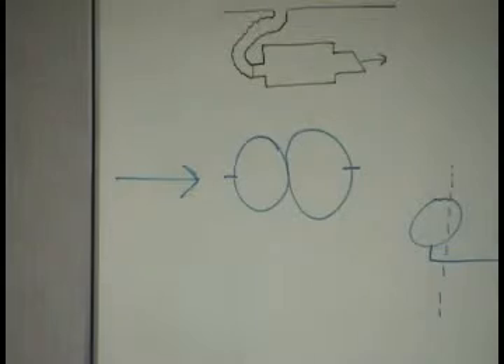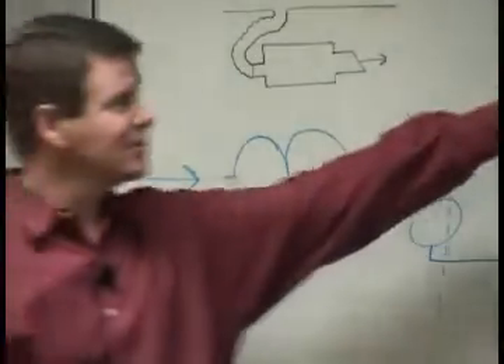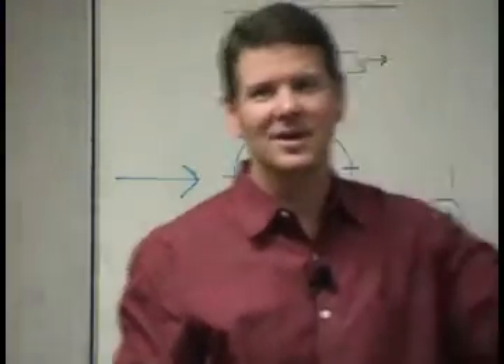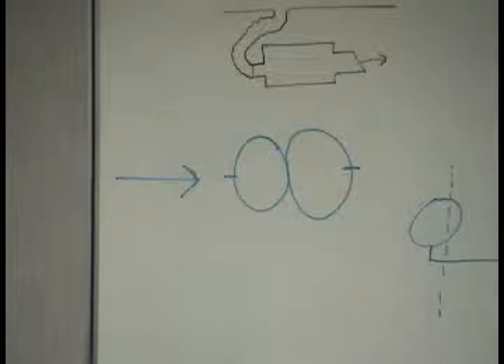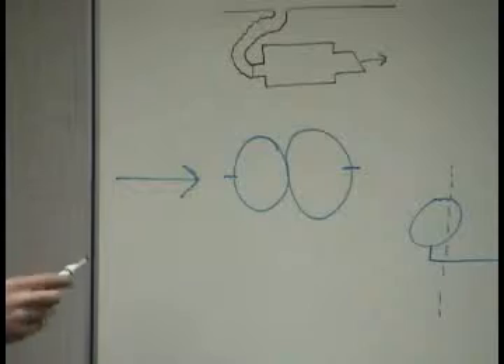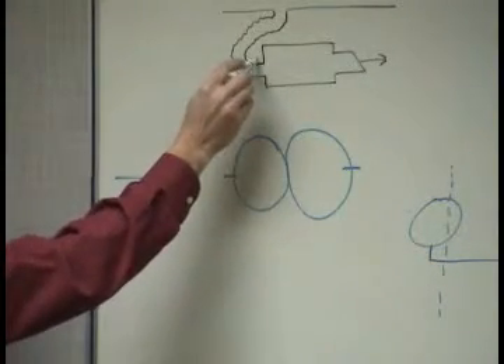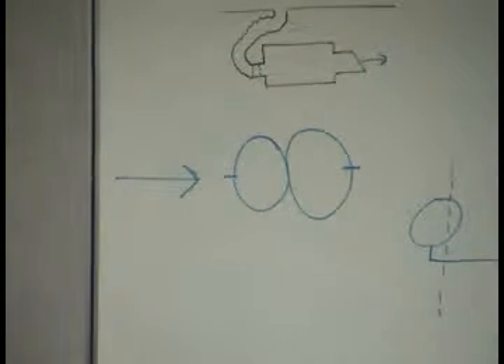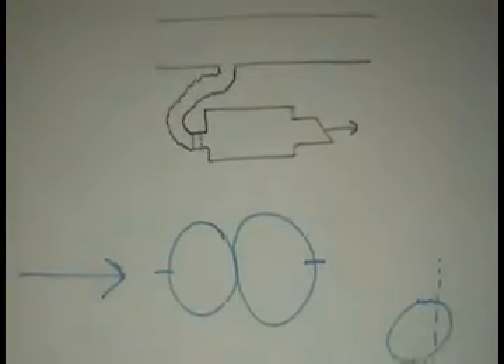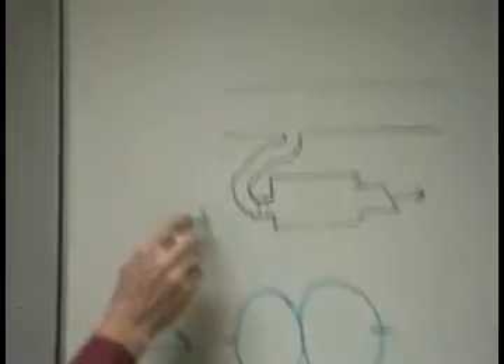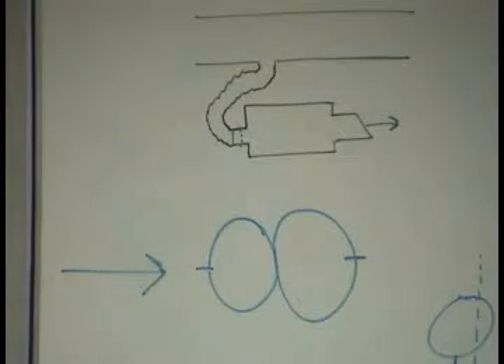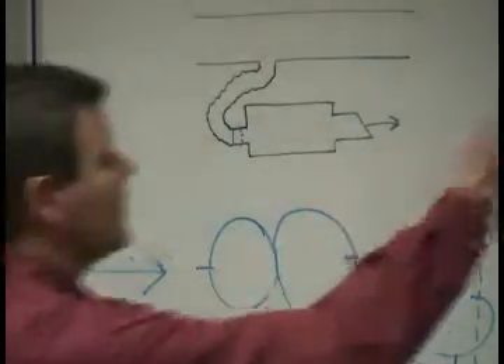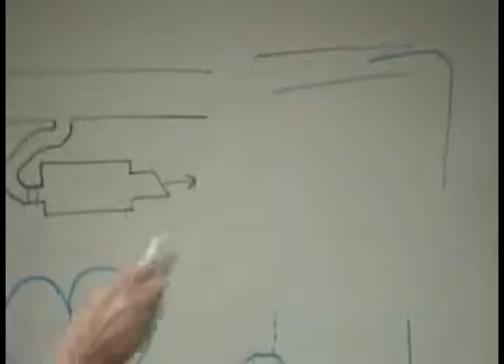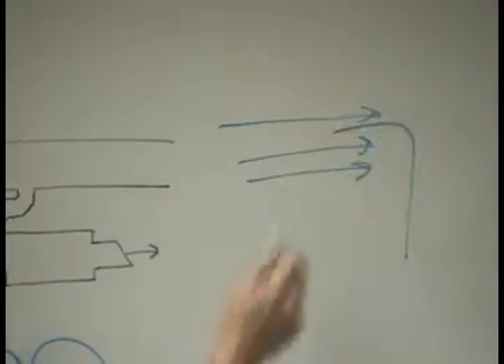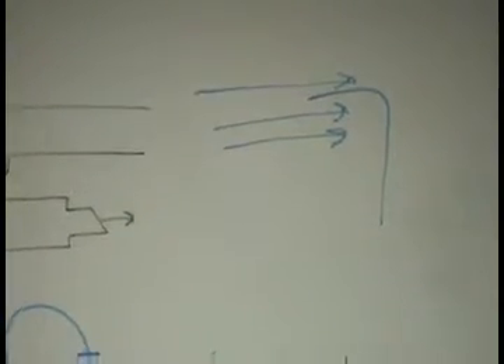We're about out of time here, but a couple things quick I wanted to touch on. If I tell this to Titus or whatever box manufacturer, they're going to come back and say, oh no, not our boxes. We have a special pickup in the inlet. Here's my box here. They always have theirs in the inlet, which is usually about this far away from the damper. And then they tell you in the instructions that they want 3 duct diameters of straight duct in front of that pitot tube. Because when I've got my pitot tube here, I've got to get some straight air, like the nice picture that I gave you in the handout here, so we can have nice laminar flow. That thing can read and give us a pretty accurate reading.